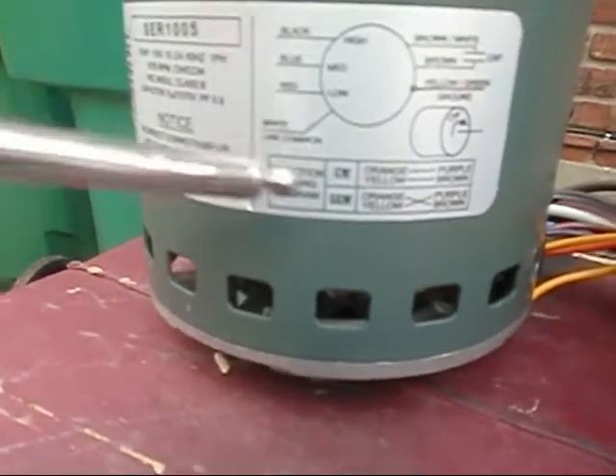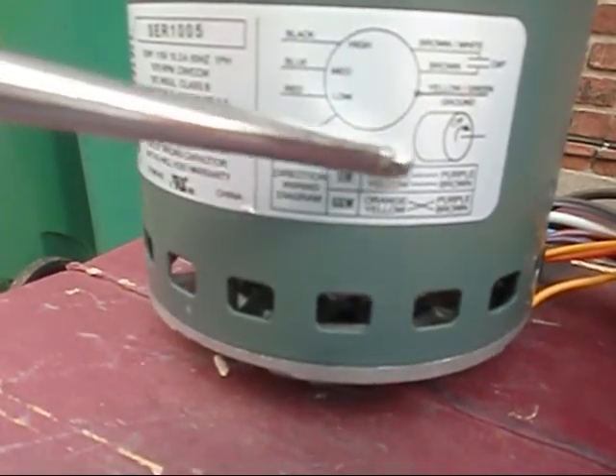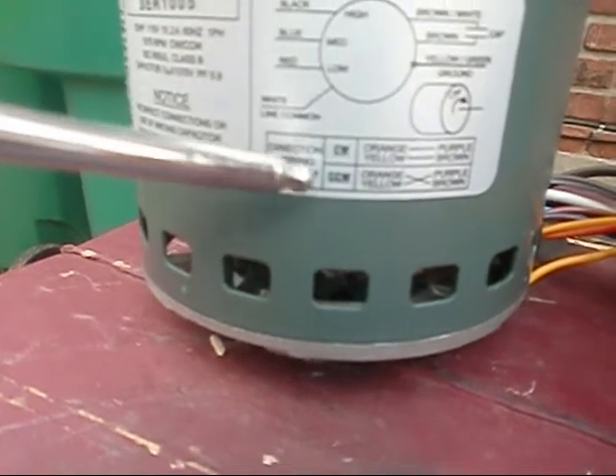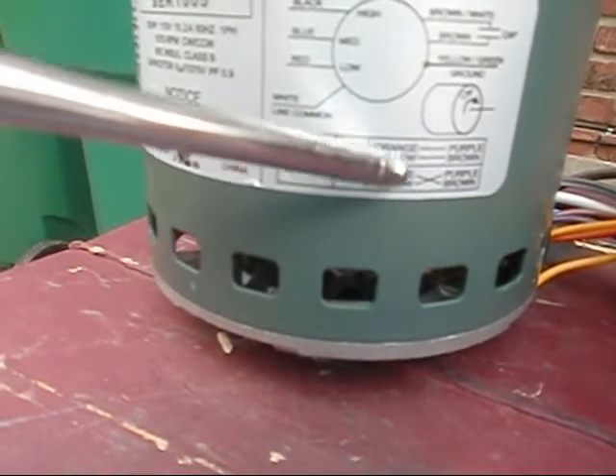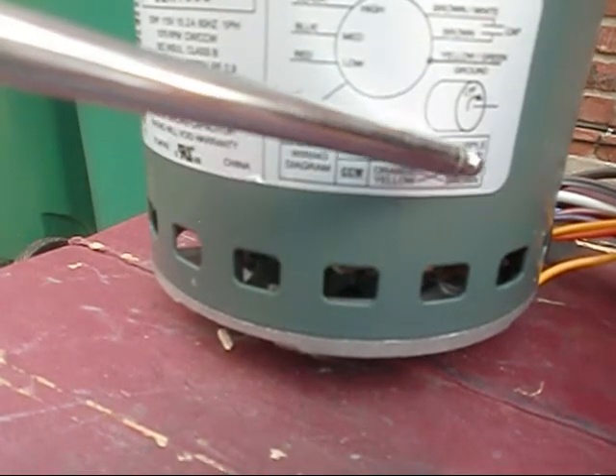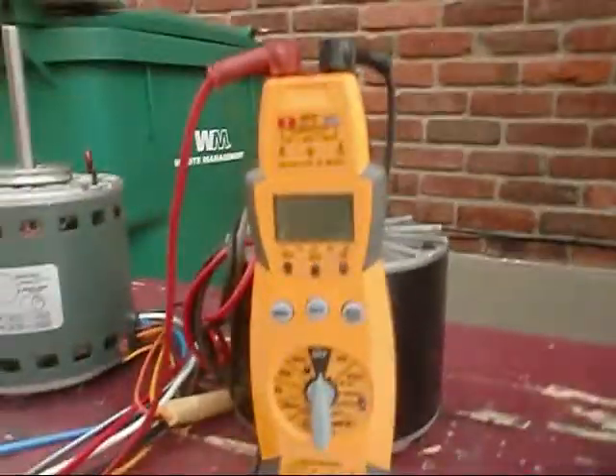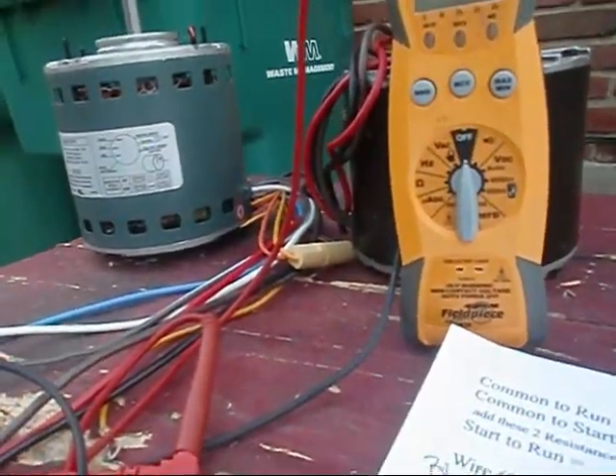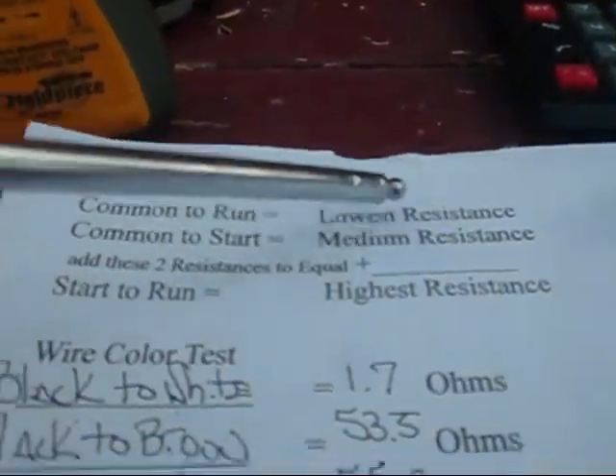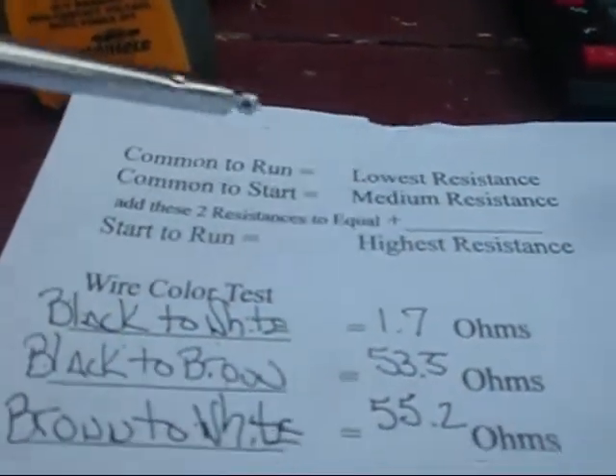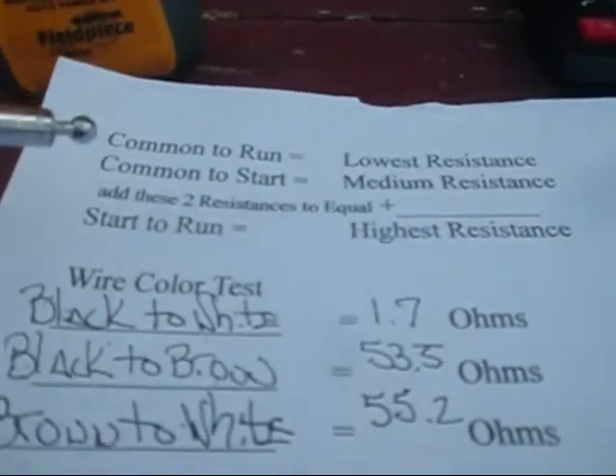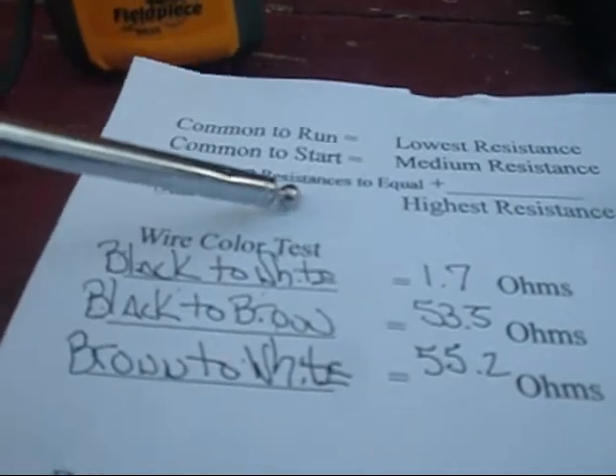Here is our multi-directional: clockwise would be orange to purple, yellow to brown. If you want to make it counter clockwise you just switch the module and it will be orange to brown, purple to yellow. What we did is we ohmed out the motor. Basically we acted like we had a three wire motor to determine what was our common to run equals our lowest resistance, common to start equals our medium resistance. Add these two resistances to equal your highest resistance which we all know is start to run.